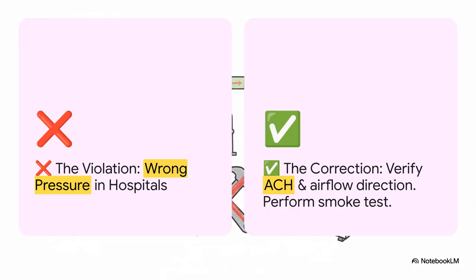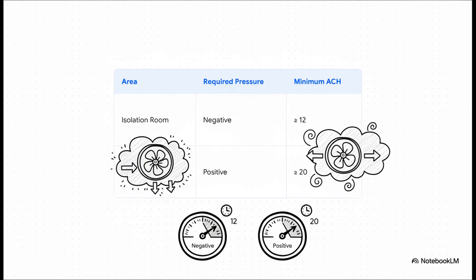Now, take that concept into a hospital, and suddenly it's a life or death situation. Getting the room pressure wrong can literally spread diseases. An isolation room has to be under negative pressure to keep germs in, while an operating room must be positive to keep germs out. I guarantee you, this is one of the most intense tests during any hospital handover. In this table right here, this is your cheat sheet from ASHRAE 170. These numbers are set in stone. Isolation room, negative pressure, at least 12 air changes an hour. Operating room, positive pressure, and at least 20 air changes. You don't just have to design for these numbers, you have to prove you're hitting them.